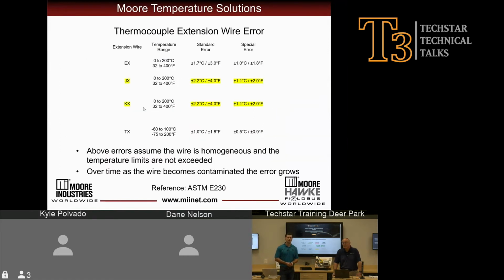So just like thermocouples that have an uncertainty, thermocouple extension wire also has an uncertainty. And just like thermocouples have a standard and a premium grade, thermocouple extension wire also has a standard or premium grade. Again, this is just looking at the metal alloys used to build the wire, and the standard grade is going to be less pure metal alloys than the special grade. Effectively, as shown with the standard grade thermocouple and special grade thermocouple, the extension wire cuts the uncertainty in half as well. You can see here we go from 4 degrees Fahrenheit of uncertainty down to 2 degrees Fahrenheit of uncertainty. And again, all of this is assuming that these wires are not yet contaminated or corroded and are right out of the box in a perfect temperature environment. So this very well could be out of specifications.